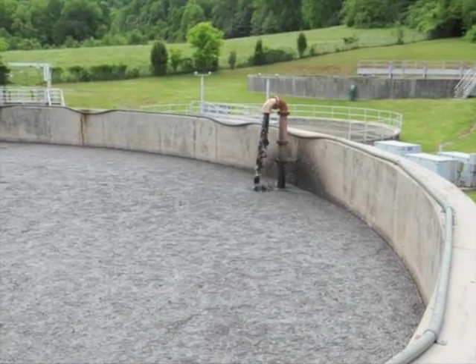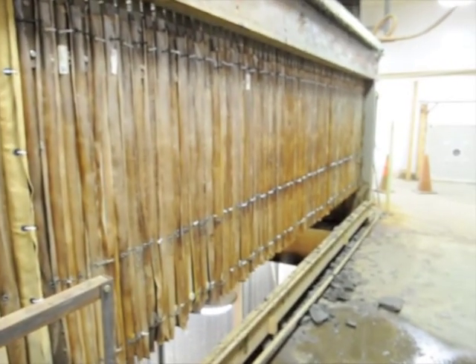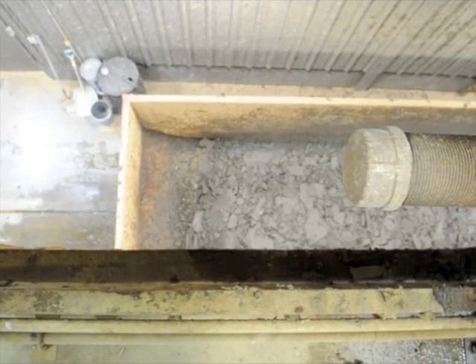What we have here is a tank that we call a digester, and it's doing exactly what its name says. It's digesting the solids or the slurry that are thrown off from the bottom of the basin. You can see the activity — the little bubbles that keep coming to the surface — that is the microbiological activity breaking down the organic matter into an inert substance that settles to the bottom. Once that settles it's drawn off, treated, and pressed as a dry cake, then hauled off and taken to the landfill.